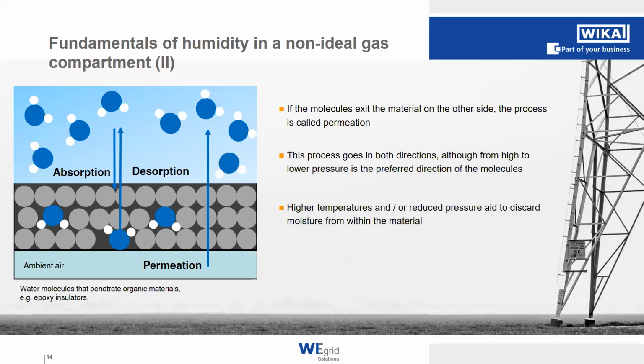Okay. Hello, everyone. This is Manuel Michele, Product Manager for Analytics. Yes, there is a special reason for the SO2 detection. In SF6 gas, we use an electrochemical cell, and there is an electrolyte inside which reacts and also dries out within 2 years' time, or a little bit more than 2 years' time. In order to make sure that you still have the same sensor performance, we have to renew the complete module, because the electrolyte reacts and then it is not available for any further reaction with the SO2 anymore. This reaction is directly proportional to the amount of SO2 you have in a gas. And if you don't have a reaction partner, which in this case is the electrolyte, you don't get a sensor signal anymore, and this is why you have to renew it. Does that answer your question?